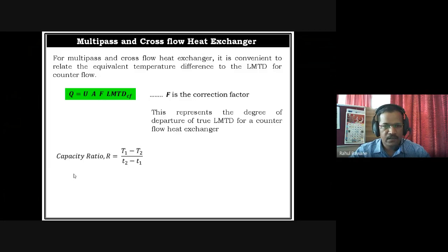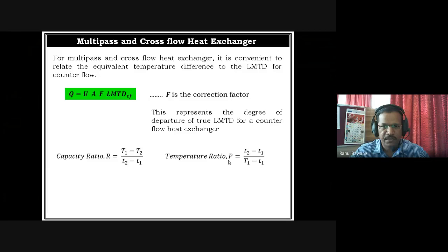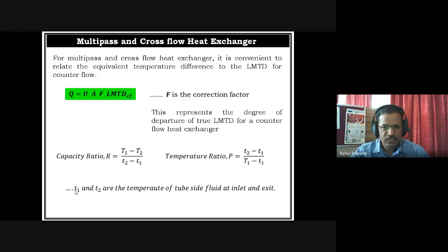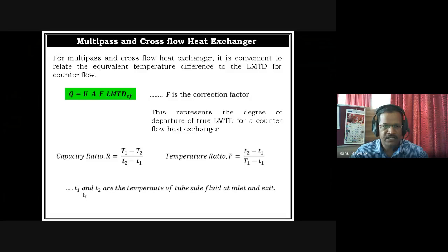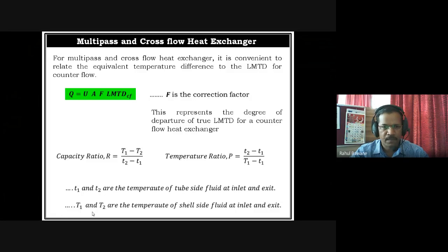To find the correction factor, we require two ratios. One is the capacity ratio R, defined as (T1 minus T2) divided by (t2 minus t1), and the temperature ratio P, defined as (t2 minus t1) divided by (T1 minus t1). Here, small t1 and t2 are the tube-side fluid temperatures — t1 is the inlet and t2 is the exit. Capital T1 and T2 represent the shell fluid temperatures, where T1 is inlet and T2 is exit.